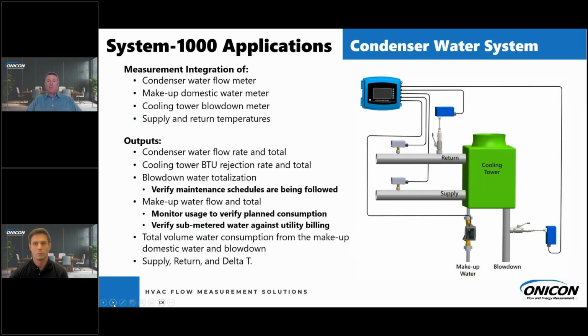If we look at the other side of the chiller, on the condenser water side, again, we're going to have a condenser water flow meter. We can add a makeup water flow meter as well for your cooling tower system. We can also add a cooling tower blowdown meter. And of course, we'll add our supply and return temperatures. Again, we're still just using one channel of the System 1000. You can mate this with the cooling side on the other channel.